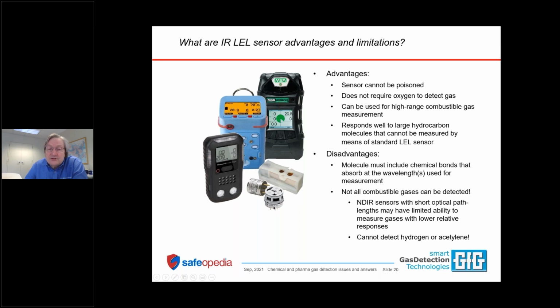Here you can see a miniaturized MEMS chip-mounted type sensor on the inside of this housing. You have a tiny, teeny little chip, which is the actual sensor. It's very small, and the optical path length is less than a tenth of a millimeter. The optical path length in the full-sized sensor is actually about 7.5 centimeters. So you have a lot more opportunity for absorbance to occur.